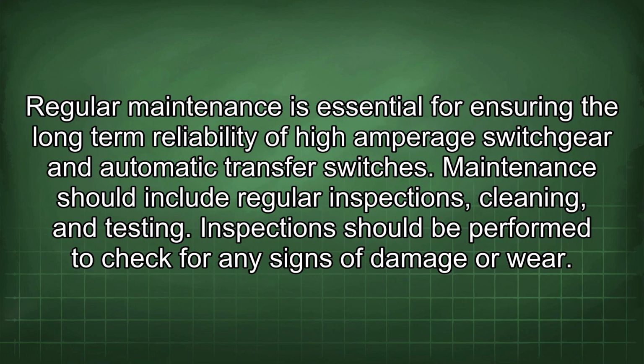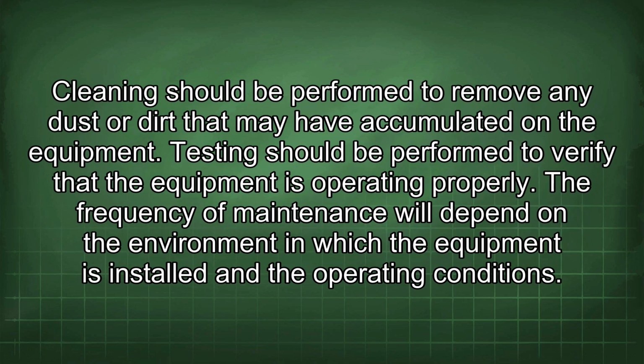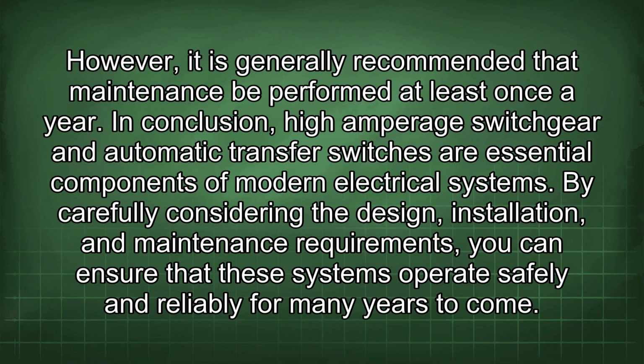Regular maintenance is essential for ensuring the long-term reliability of high amperage switchgear and automatic transfer switches. Maintenance should include regular inspections, cleaning, and testing. Inspections should be performed to check for any signs of damage or wear. Cleaning should be performed to remove any dust or dirt that may have accumulated on the equipment. Testing should be performed to verify that the equipment is operating properly. The frequency of maintenance will depend on the environment in which the equipment is installed and the operating conditions. However, it is generally recommended that maintenance be performed at least once a year.